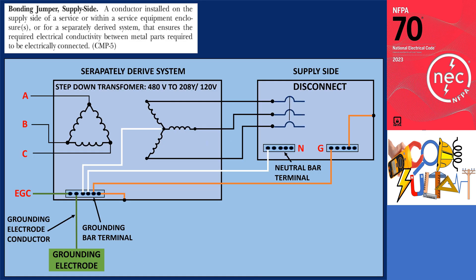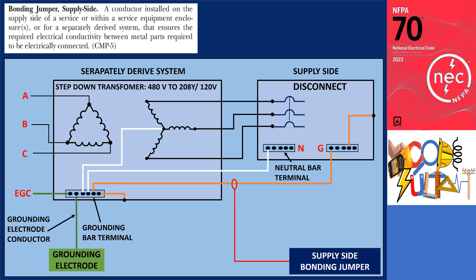A supply-side bonding jumper is a conductor installed on the supply side of a service or within service equipment enclosures, or for a separately derived system, that ensures the required electrical conductivity between metal parts required to be electrically connected. Equipment such as metal enclosures, raceways, and cable trays that are part of the supply-side conductors need to be bonded. For example, in the illustration of a wiring arrangement for dry-type transformers, the bonding conductors connecting the grounding bar terminal of a separately derived system to the first disconnect are considered supply-side bonding jumpers. Additionally, the bonding at the first disconnect enclosure is also a supply-side bonding jumper.